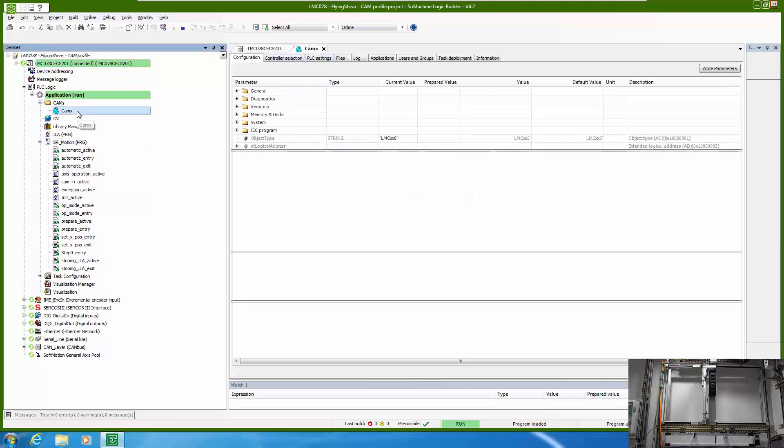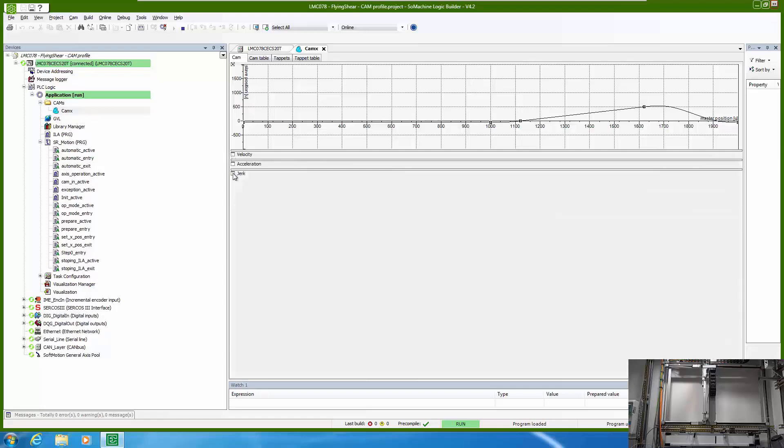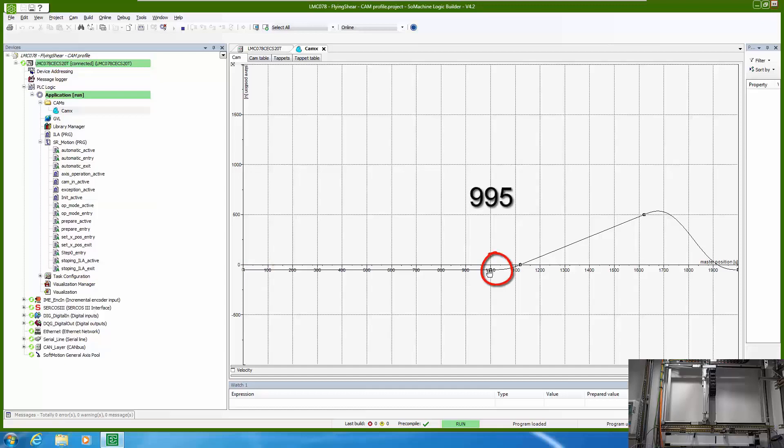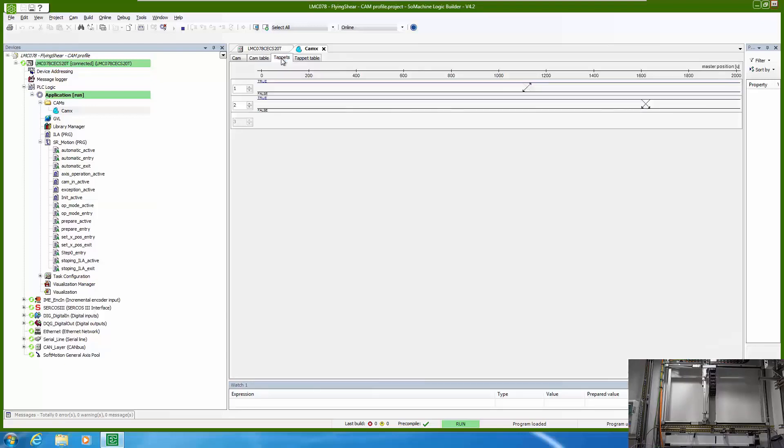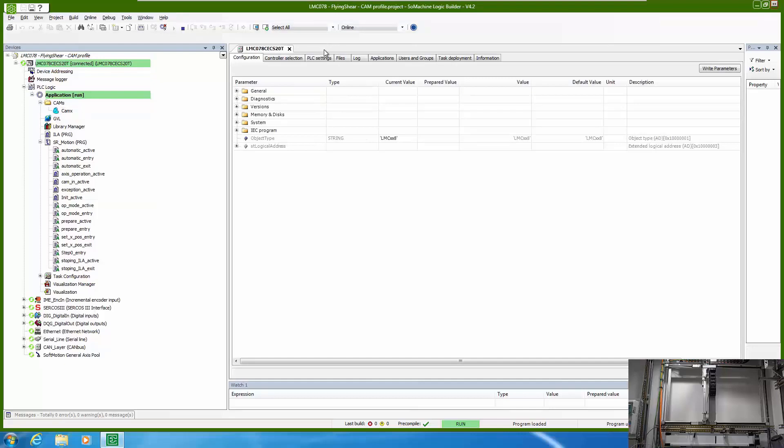Then we have cam profile and here you can see that we have positioning profile of our flying shear. So in the beginning we are rotating inside this field until we detect the touch probe. When we detect the touch probe we set the position of slave to 995 and then we run a profile and again we are waiting for a touch probe. Here you can see the settings of our cam profile and also tappets which will indicate when we will switch on and off. That means when we will go in one or other direction with vertical axis.